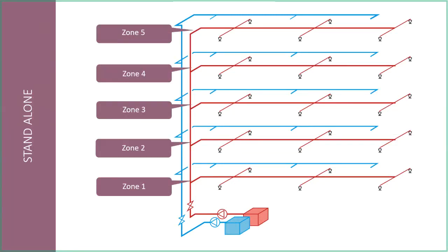And then if you've got a multi-storey building, which is what I'm going to be concentrating on today, multi-storey, large blocks of flats, large residential premises, then typically what you would do is have a different zone on every floor. This is quite similar to commercial sprinklers under 12845, where you have a simple isolation control valve on the ground floor where you're going to do your flow test and other bits and pieces. Then at each floor you have a zone which comprises an isolation valve and a flow switch, so that you can isolate the supply to each floor.